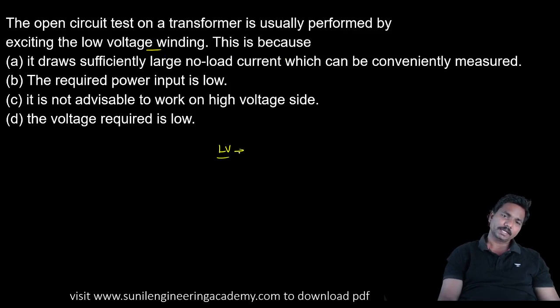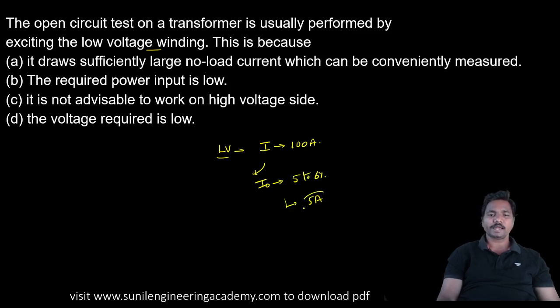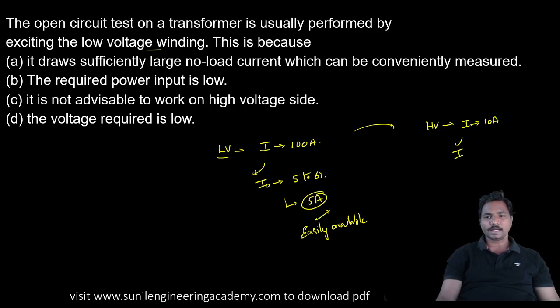If it is the LV winding, then the current will be higher. Let us take for example 100 amps. Then what is the I naught? I naught is nearly 5 to 6%. So let us take 5%, which means 5 amps. 5 amp meters are easily available. In the same way, if the test is performed on HV side, high voltage means current is less, for example 10 amps. Then I naught is 5%, so 0.5 amps. A 0.5 amp range means we have to use a 0 to 1 amp meter, which has less availability and is costly also.